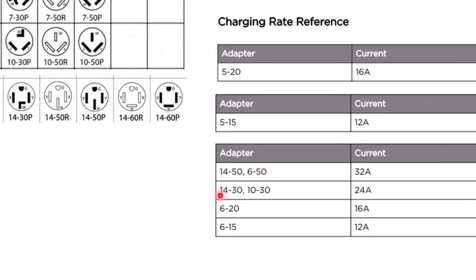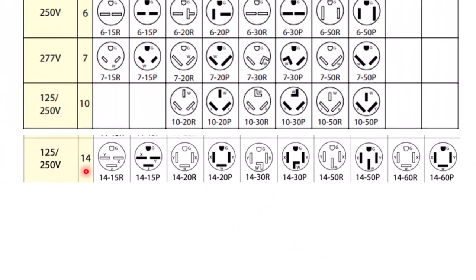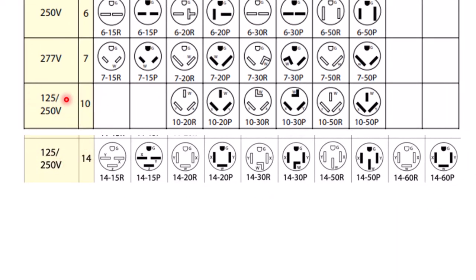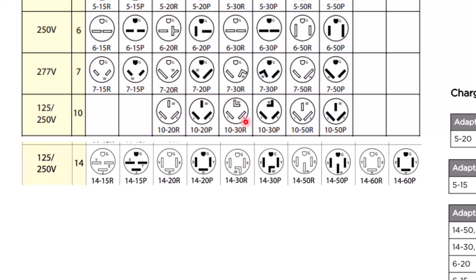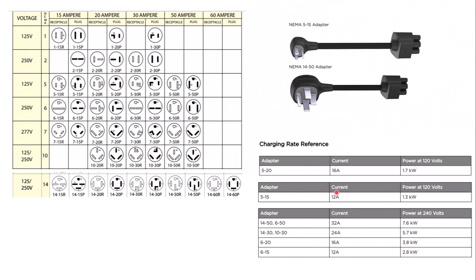And a 10 is similar to the 14, except it does not have a ground. So if you look here, it's the same thing as the 14. It's 125/250. But if you look here, there is no ground. So if you look, for instance, this one, it's a 30 amp. And if you look at 30 amp column here, you can see that this one has a ground, the NEMA 14s, but the NEMA 10s do not have that ground. So that's the difference. So when you purchase the adapter, you just have to make sure that you get the correct rating so that it fits the outlet that you have or you're planning on installing for this EV charger.